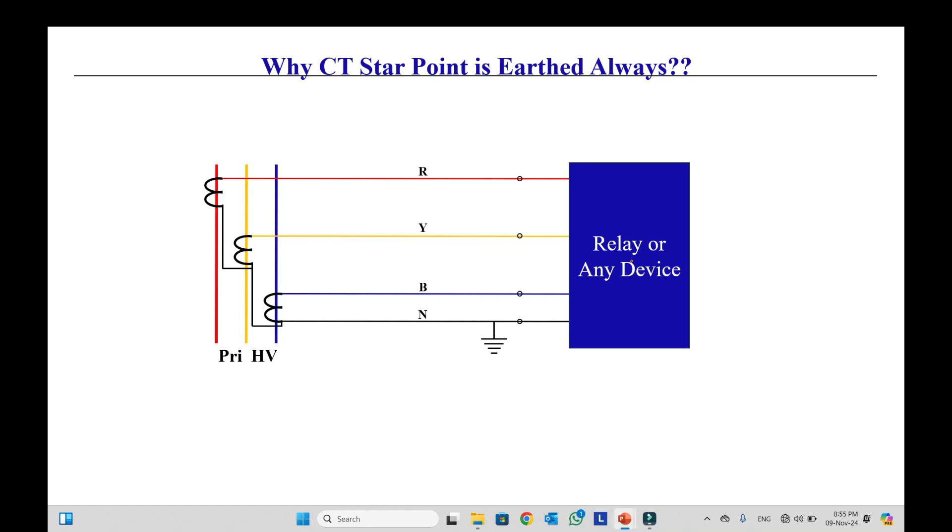It could be a relay or any other device such as a meter. So we have this concerned point of neutral. Actually this is our star point and it is earthed. We can see earth is connected. We have the high voltage or extra high voltage or medium voltage primary side of the CT, and the secondary side is low voltage.